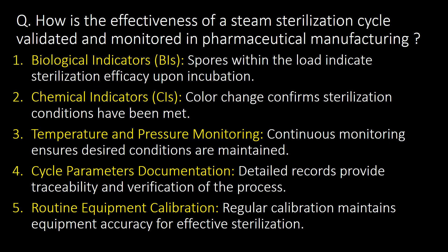How is the effectiveness of a steam sterilization cycle validated and monitored in pharmaceutical manufacturing? There are mainly five methods: first, using biological indicators; second, using chemical indicators; third, temperature and pressure monitoring; fourth, cycle parameters documentation; and fifth, routine equipment calibration.